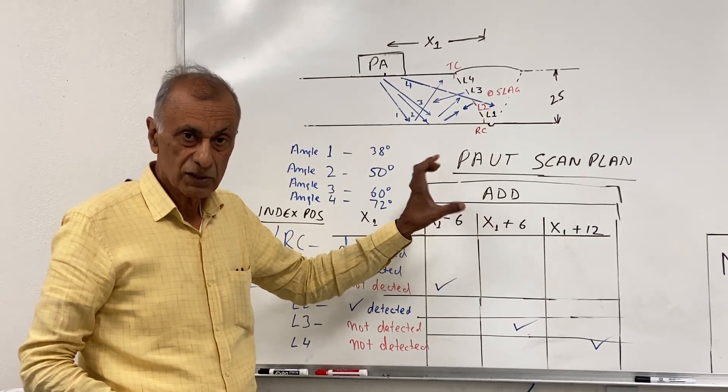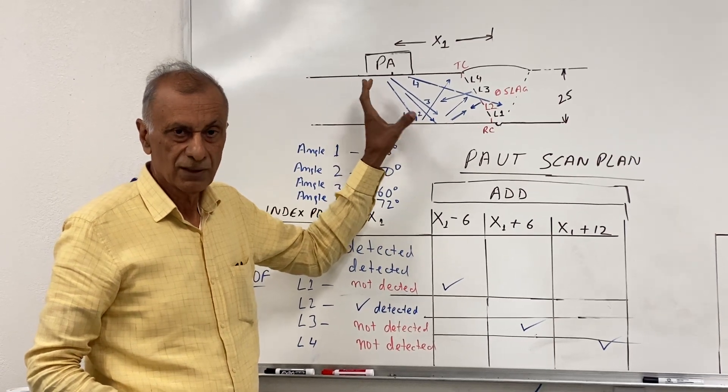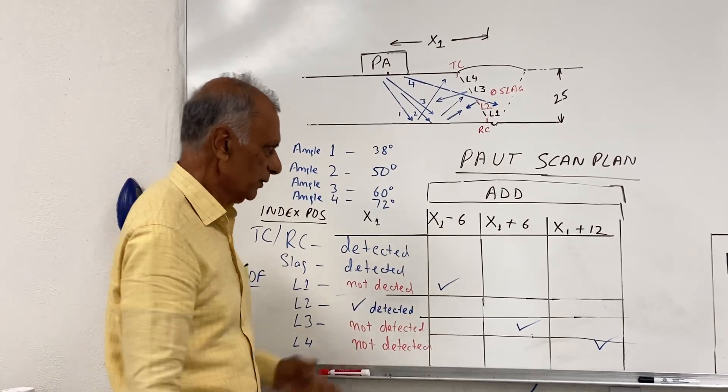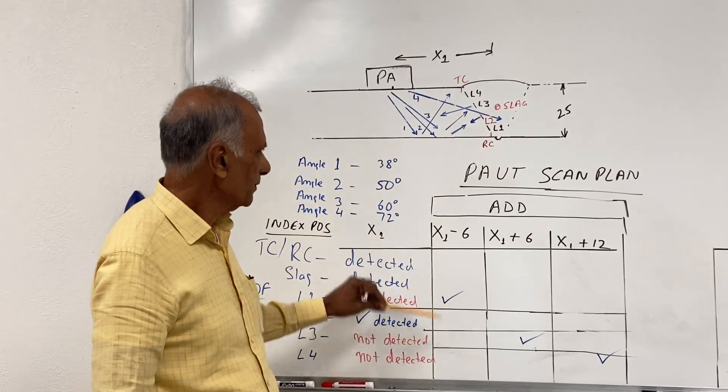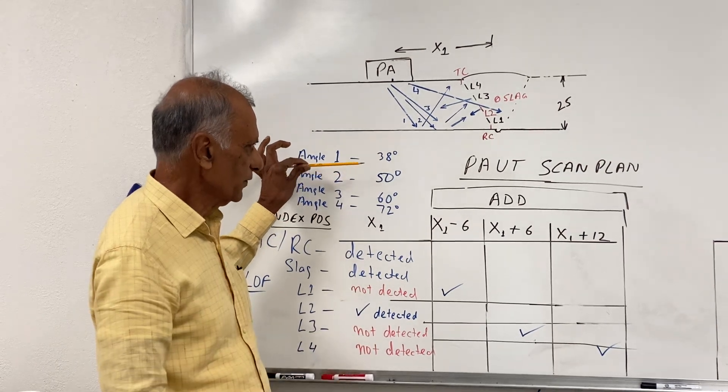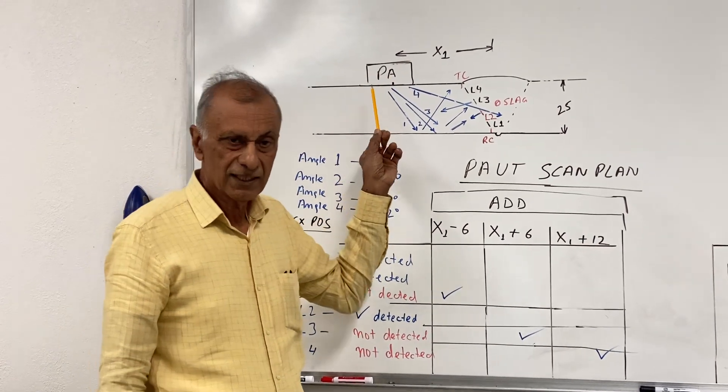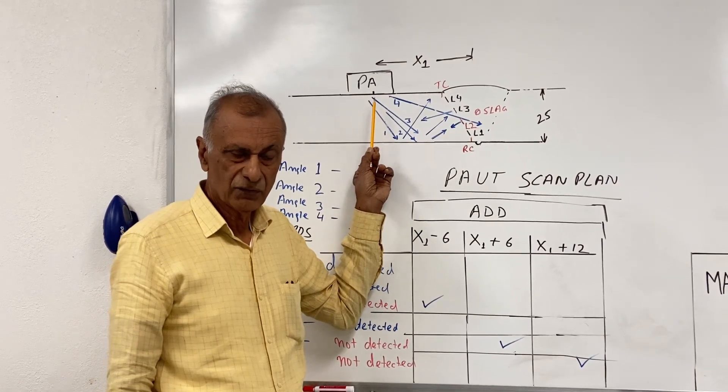Now if you are looking for smaller lack of fusion flaws, then you have to reduce this pitch, which is the 6mm, you may have to reduce it to 4. So that, you have to decide on your own. But basically, in this lecture, what I wanted to emphasize is that a single index position is not the right way to do the phased array.